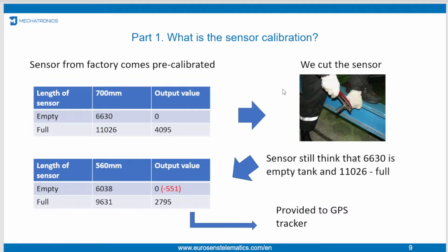And by default, the sensor from the factory is pre-calibrated. So we are getting these values, but we need to fit the sensor in the tank. And after cutting, these values are reduced, and from this output range of internal values we will get this one. On a full tank, a cut sensor will give not 11,000 but only 9,600, and based on the stored calibration table and sensor factory calibration, we will get not 4,000 but this value.